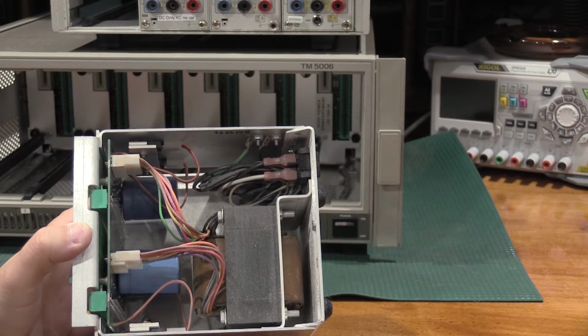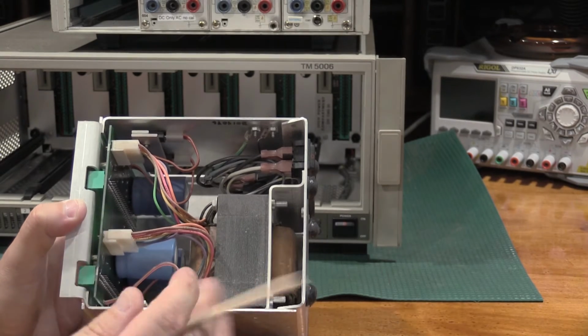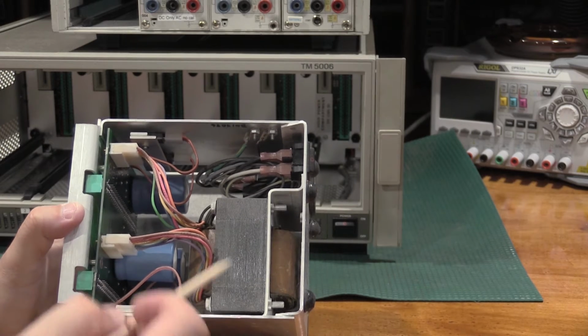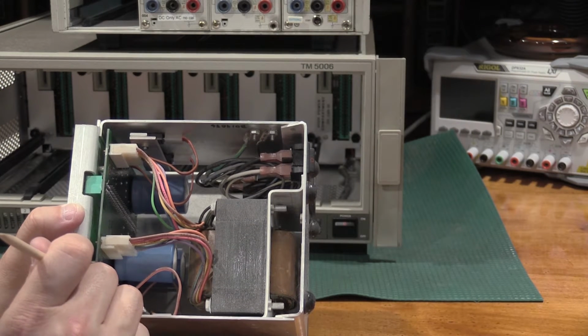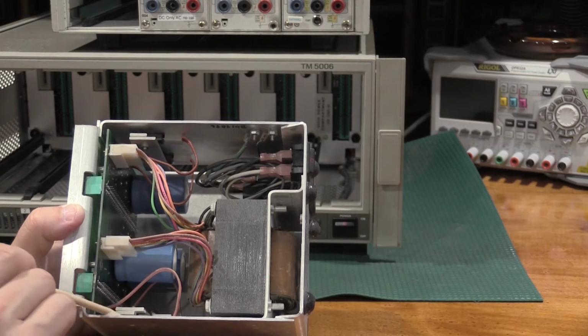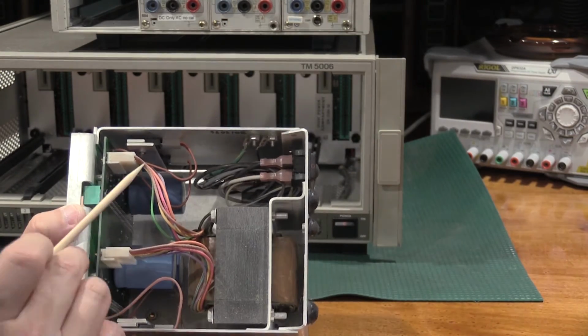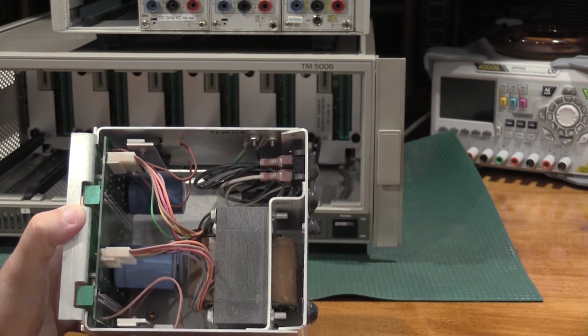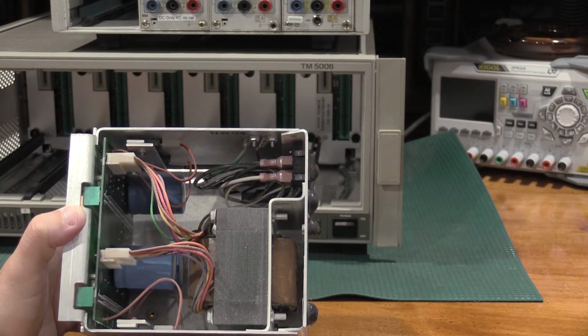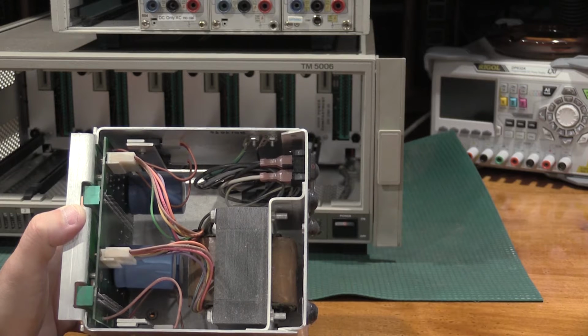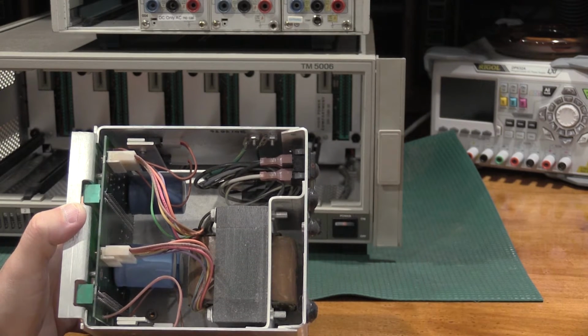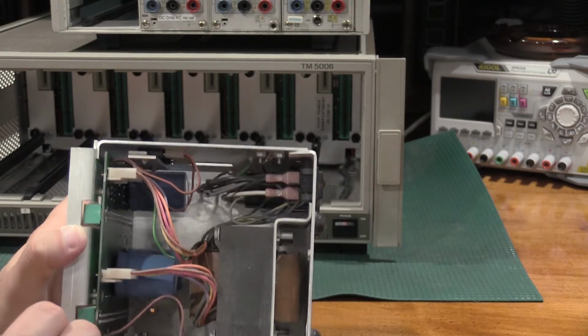And if we're doing ultra-low distortion measurements, that could come into play. The other thing to note when picking up a power supply, any power supply, is every power unit for the 500 and 5000 series has pass elements in the frame. Now the high power bay has some high power transistors, and then they have, actually they're all pretty decent power, but they have some really heat sinked and high power transistors for the high power bay and the 5000 frames. In this particular one, because we don't have a high power port, we have the regular pass elements.